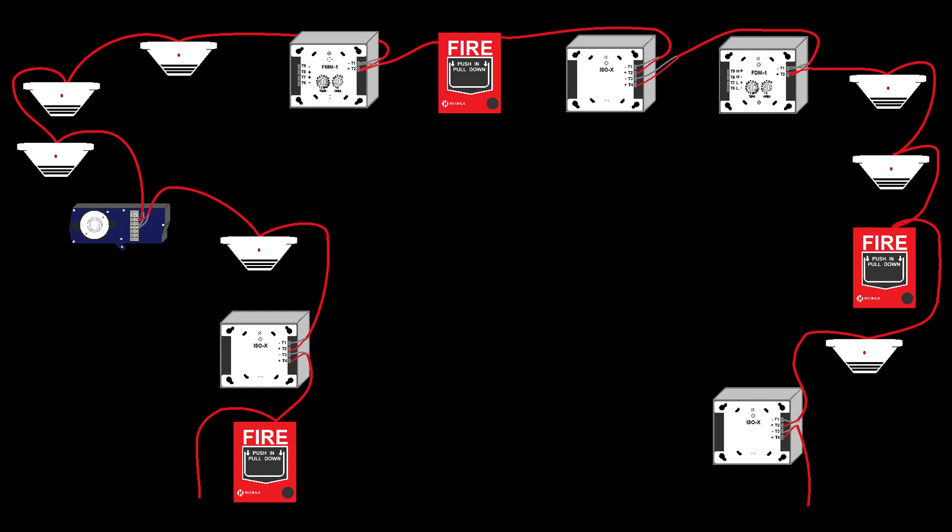Isolator modules work in pairs. If there is a short in the circuit between two isolator modules, they will remove that portion of the circuit from the loop, protecting the remainder of the loop from being affected by the short.